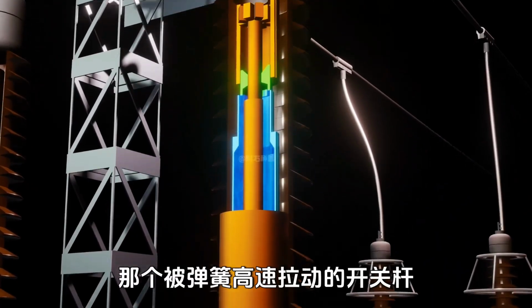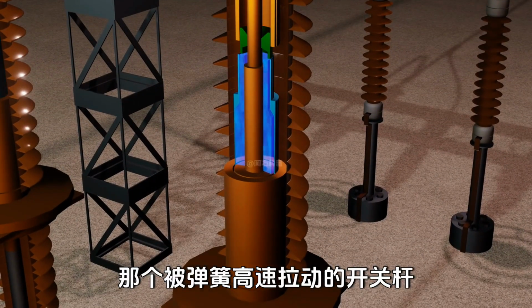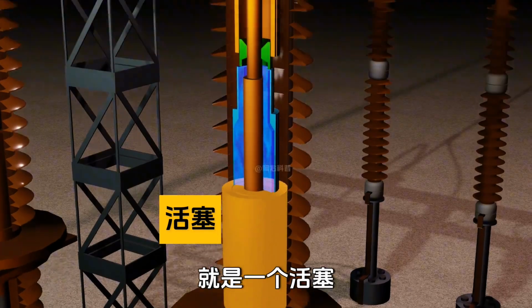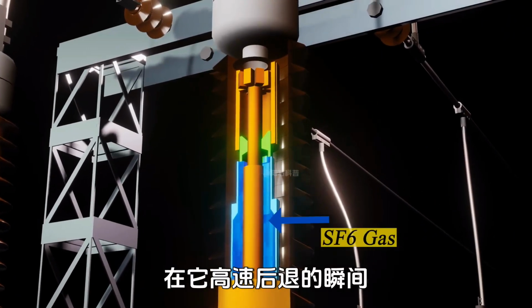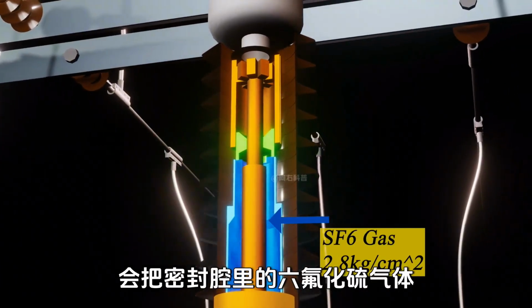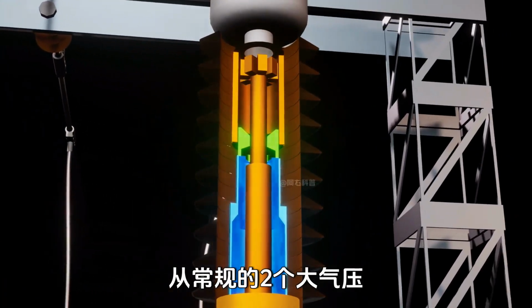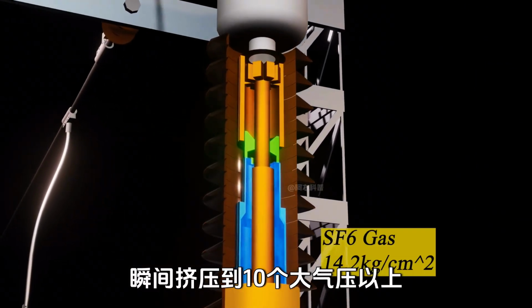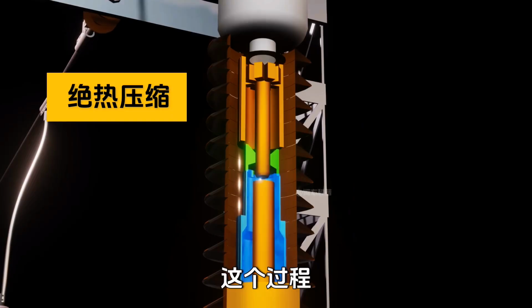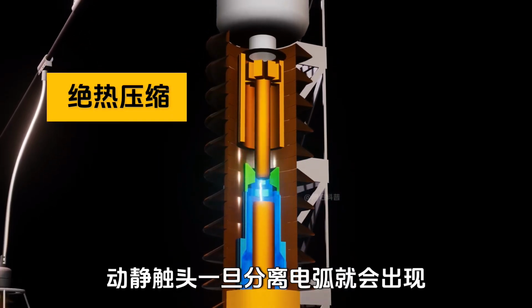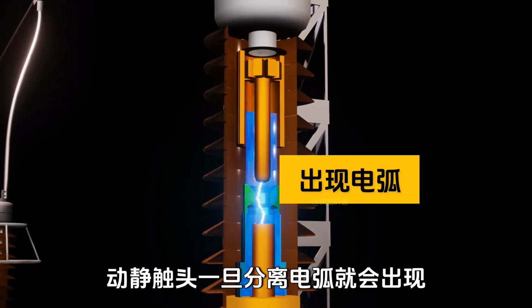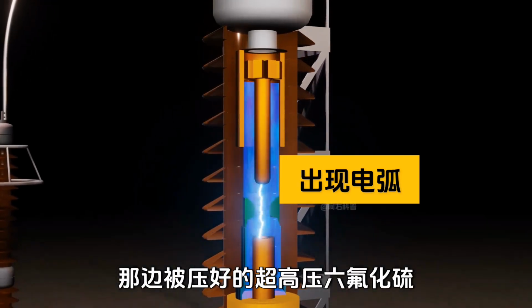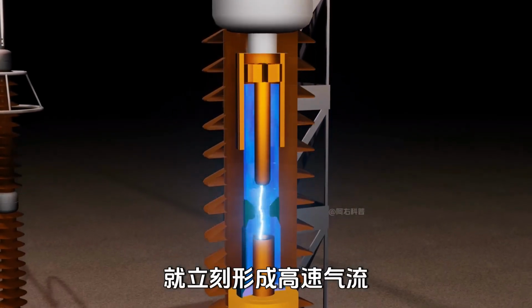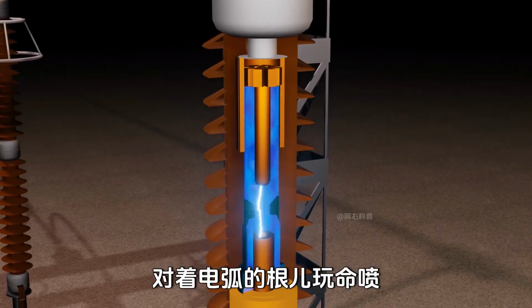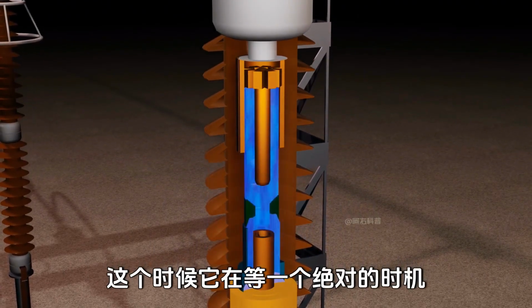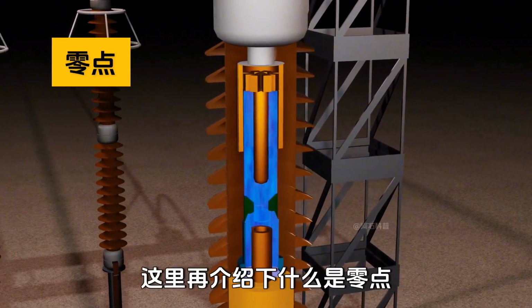And this is the coolest part. The switch rod connected to the spring acts like a piston. As it snaps backward at high speed, it compresses the sealed SF6 gas chamber from just 2 atmospheres up to more than 10 atmospheres. This process is called adiabatic compression. Compression without losing heat. The moment the contacts separate, an electric spark appears. Right then, the high-pressure SF6 gas rushes out at high speed, blasting directly at the spark. Now it's waiting for a critical moment, the current zero point.